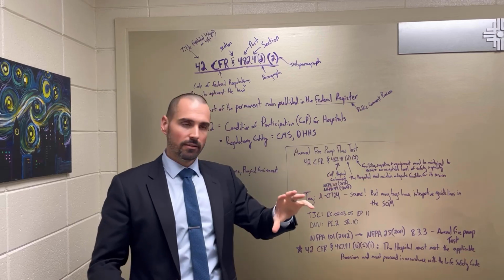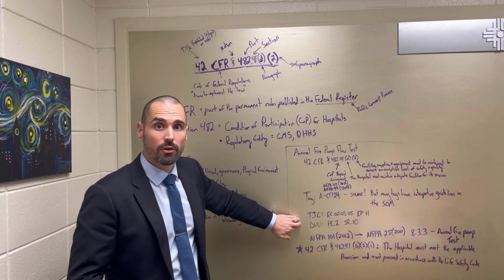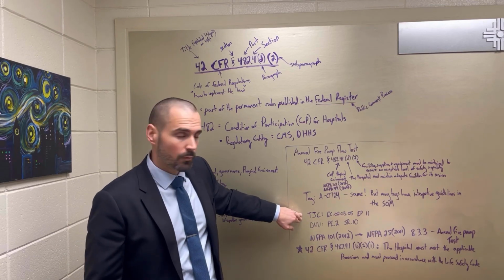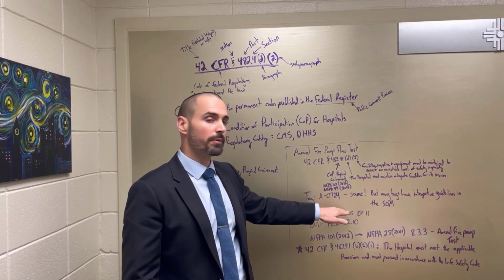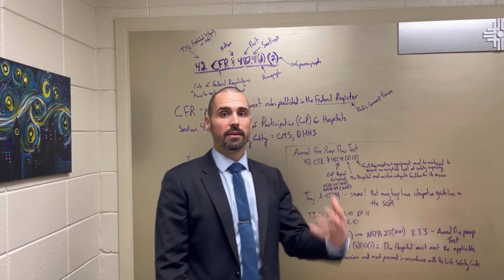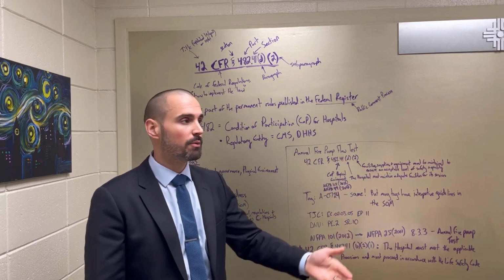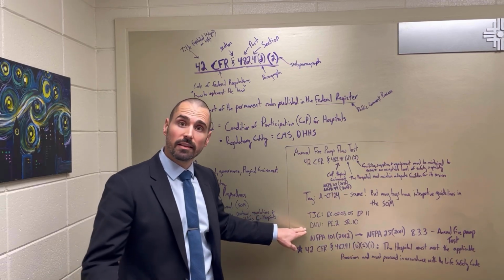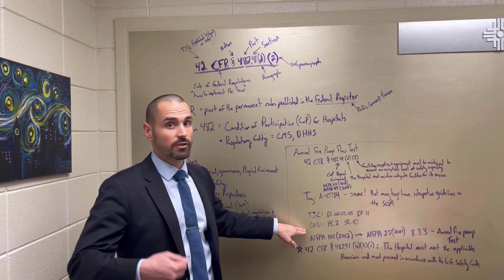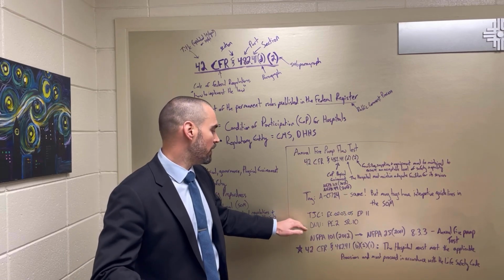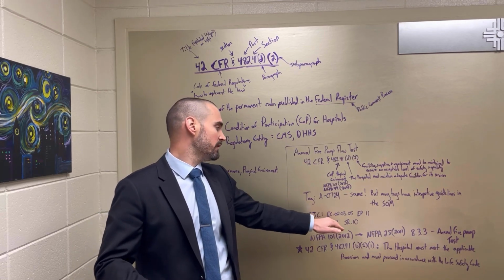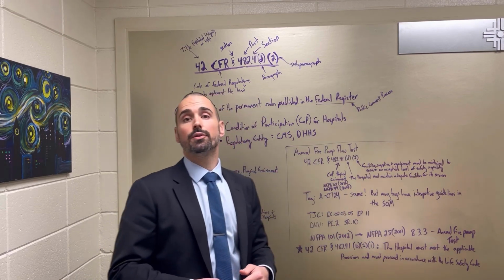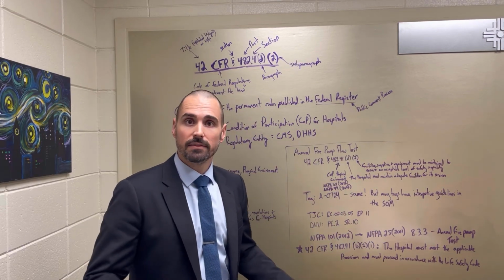Okay, a little bit more detail, all right? And then you have accrediting organizations. I've got a few here just to talk through. Joint Commission, which says EC.02.03.05, EP 11, and it's very specific on theirs. It says you have to, every 12 months, do an annual flow of your fire pump. And then you have DNV, which is a little bit less prescriptive, because it's just a different model of how they operate. They have Physical Environment 2, which is the guideline, SR.10, and it just says that you have to test and inspect your life safety systems, right?